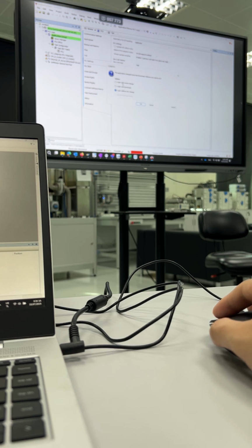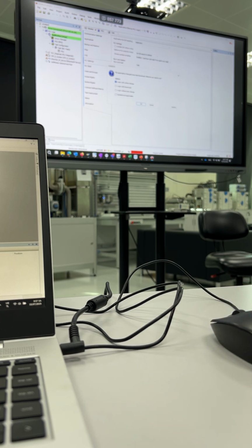Okay. And then of course you can also download without changes, so you will just use back the previous download. Then you see there is update boot application. Update boot application means that it will store the program into the PLC memory. So when you power cycle the PLC, you will still have this program. If you do not download with the boot application, it will not have a program, or it will restore back to the previous PLC program.